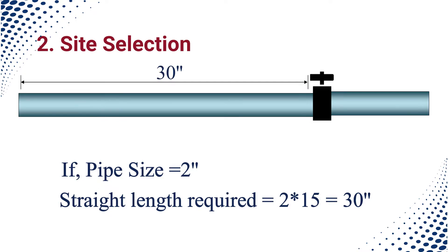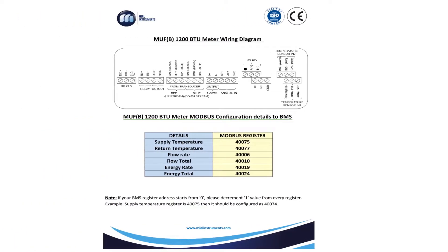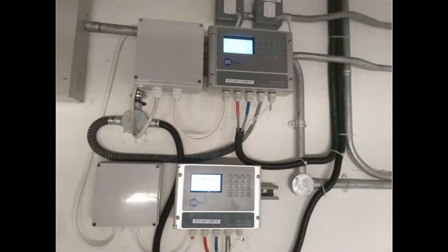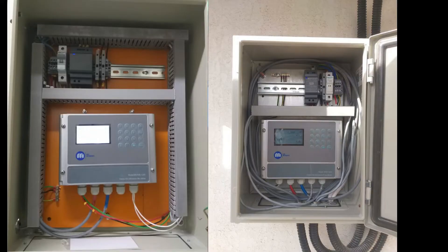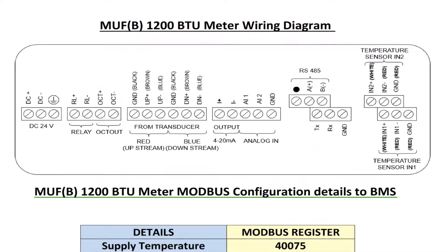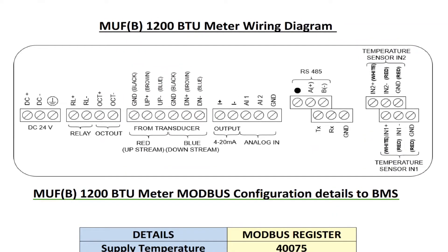Before starting the wiring, bring the wiring diagram from the document envelope and must go through it. You can also download the wiring diagram by scanning the QR code pasted inside the display unit. Fix the transmitter unit near to the site selected for flow sensor installation and wire up the meter as per the wiring diagram. Use a 24-volt DC power supply with proper earth to energize the meter. The next step is transducer installation.